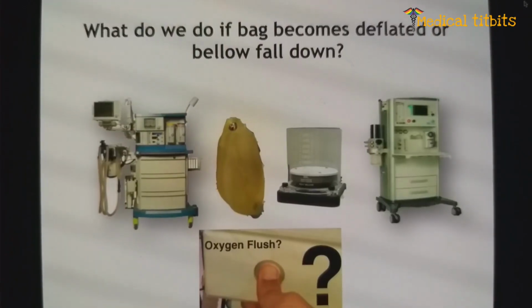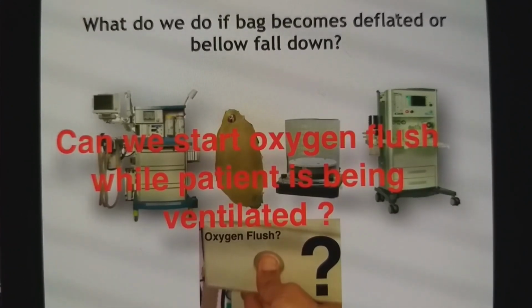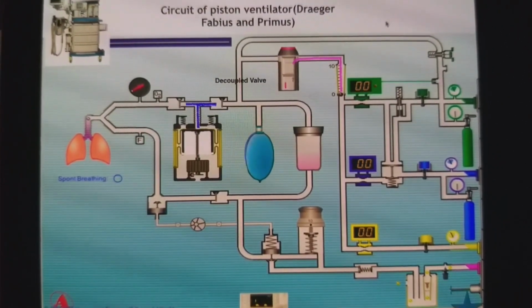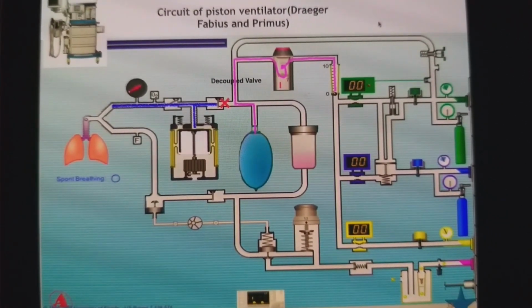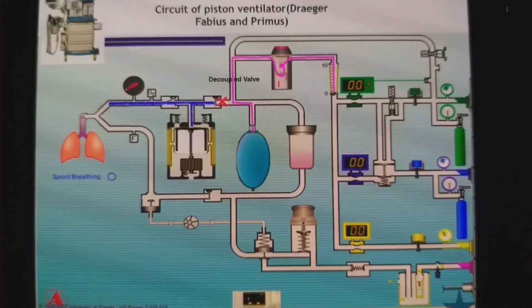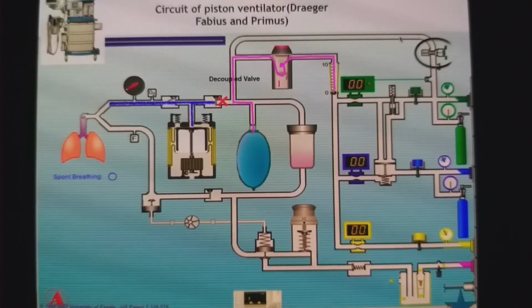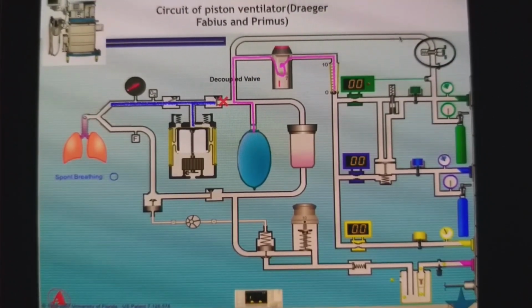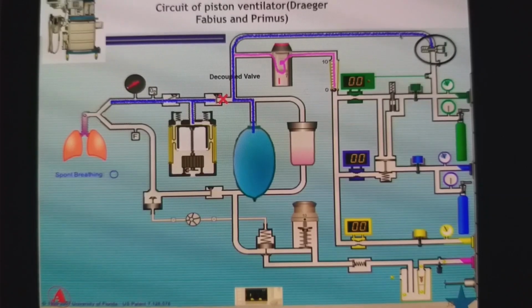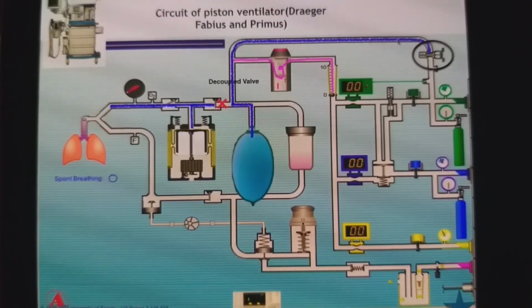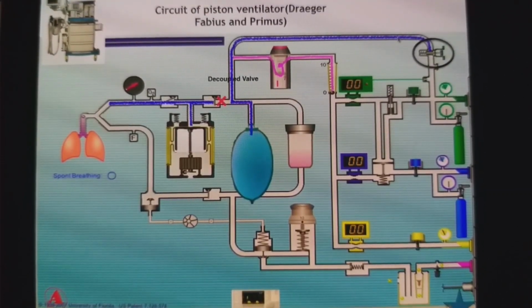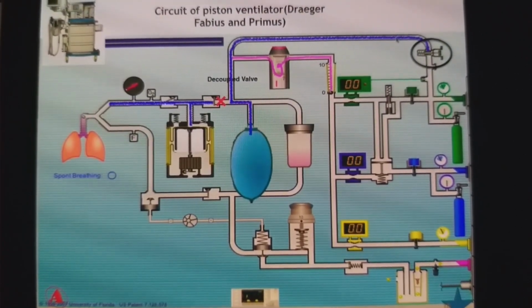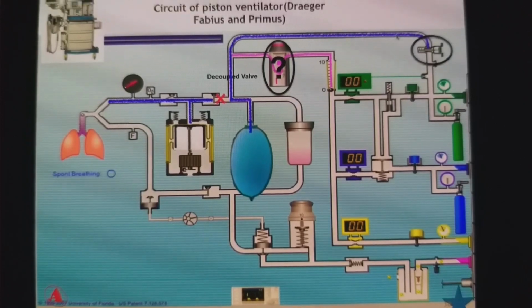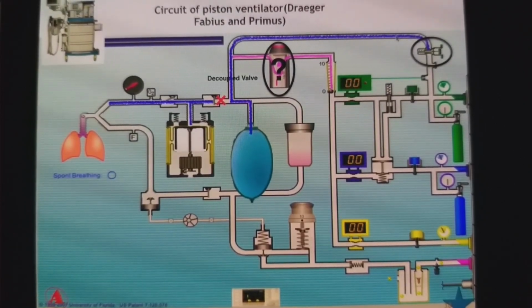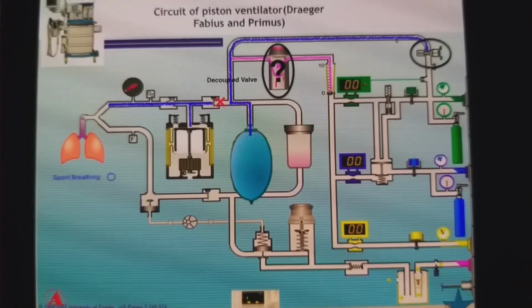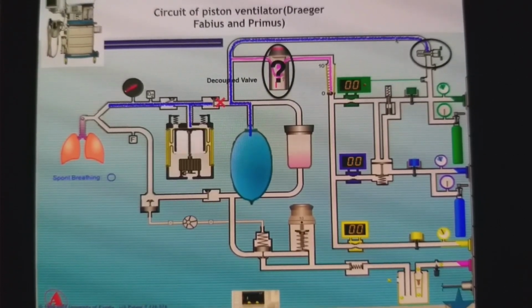Now let us take this scenario that we can press the oxygen flush. Let's see whether we should flush the oxygen if there is a gas volume deficiency. So this is again a Draeger circuit with decoupled valve. If I am pressing the flush, what will happen? Now I am pressing the flush. What will happen? If you press the flush, during inspiration, nothing is going to the ventilator. Ventilator will continue to deliver its own 500 tidal volume. The extra gas will go to the reservoir only. Nothing will go to the ventilator. So patient will not have any change in the delivery of tidal volume because nothing is missing in the inspiration. The only problem would be that it bypasses your inhalation anesthetic. It will bypass your vaporizer and it will directly go to the reservoir.